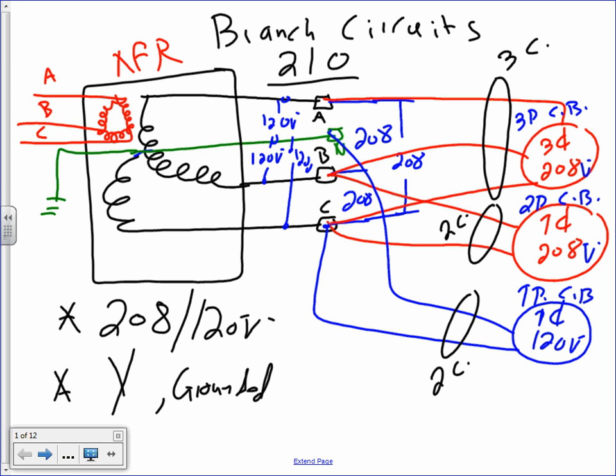Okay. Now, your system is going to sit like this. So I have a 4-wire system with a neutral. Can you guys see the neutral coming in? How many wires do you bring from the transformer into your panel? 4 wires. 3-phase and neutral. What happened to the ground and the grounding? Nothing. Mistake number 1: between the utility transformer and your building, you only carry 4 wires. The 3 hots and a neutral.